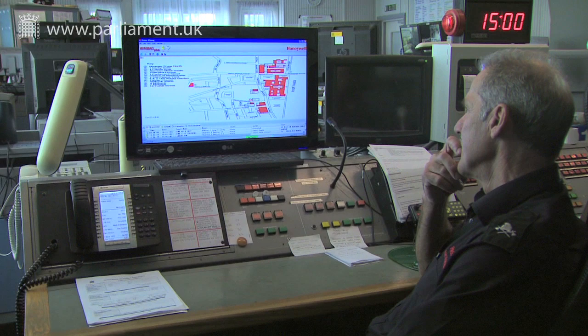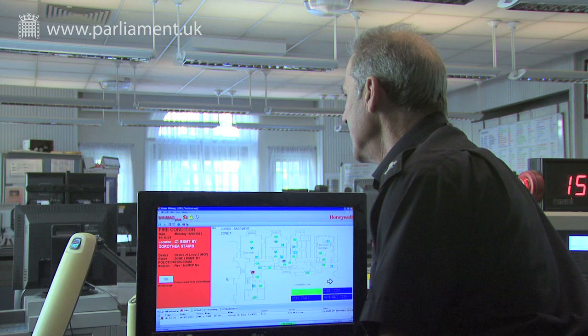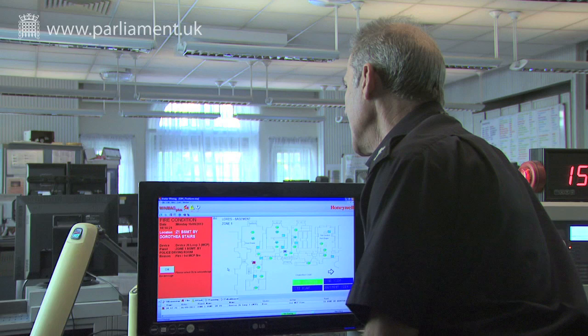They're part of the infrastructure that links the fire alarm system to the control room, but many of them only give very limited signals. Also, this infrastructure services the entire estate, not only the Palace. And because of its age, it won't support the more modern, data-heavy systems which have been installed.